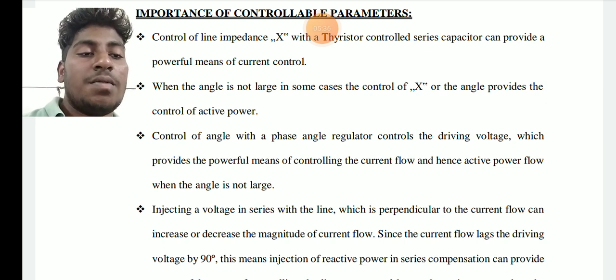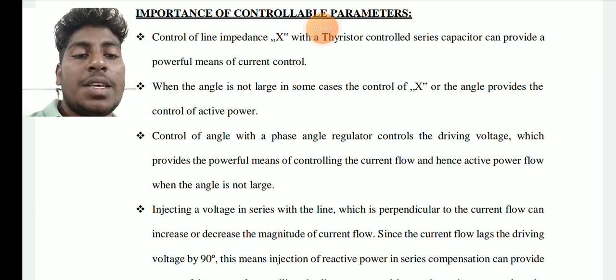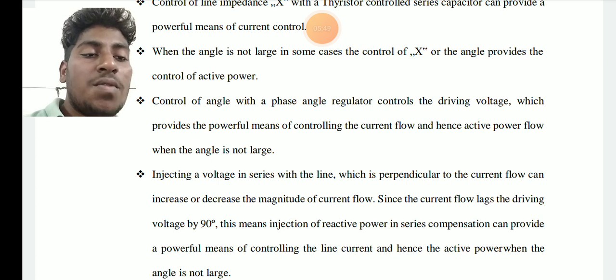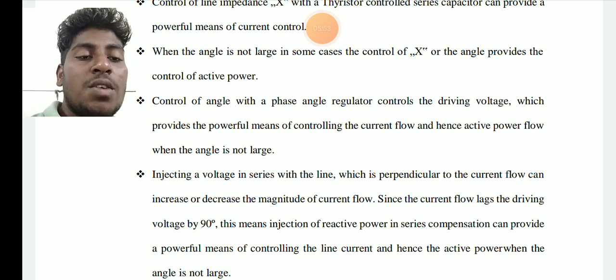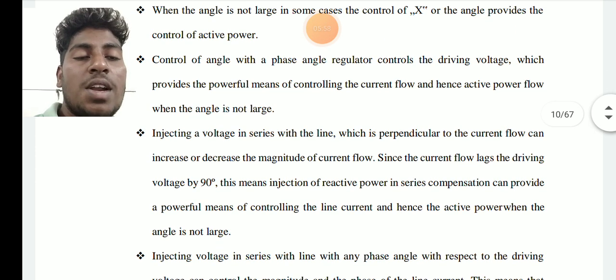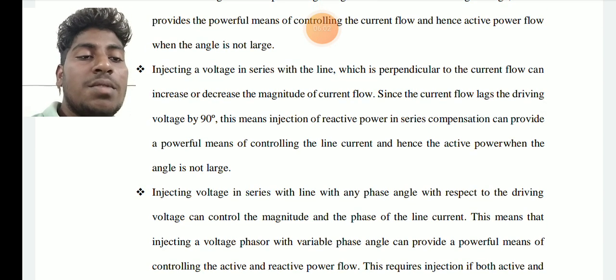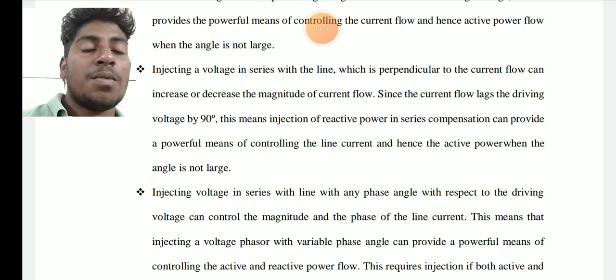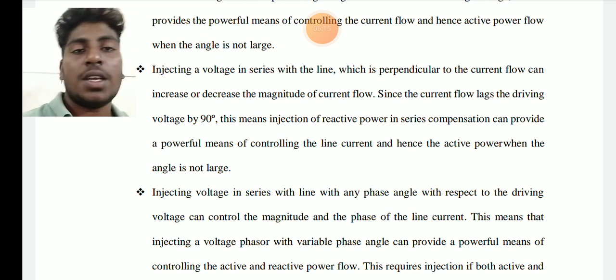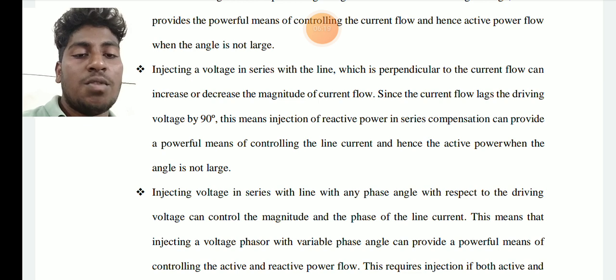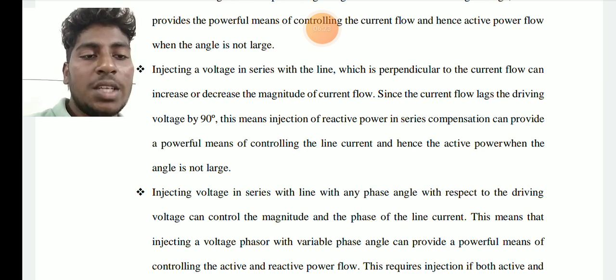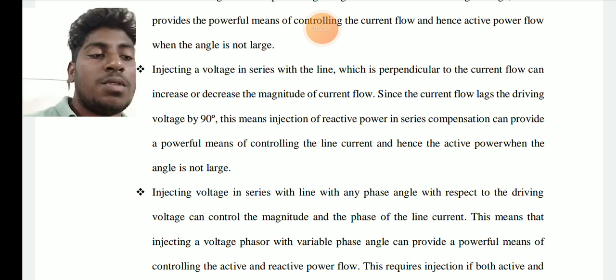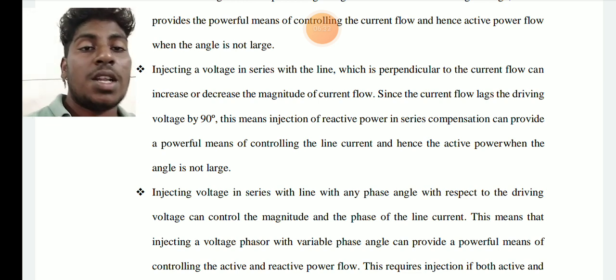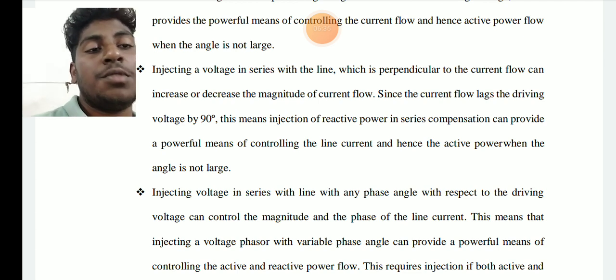Injecting voltage in series with a line, in quadrature with the current flow, can increase or decrease the magnitude of the current flow, since the current flow is lagging the driving voltage by 90 degrees. This means of injection of a series compensation can be provided as a powerful means of controlling the line current and hence the active power when the angle is not large. Injecting voltage in series with the line with a variable phase angle with respect to the driving voltage can vary the voltage magnitude and the phase of the current, providing a powerful means of controlling both active and reactive power.